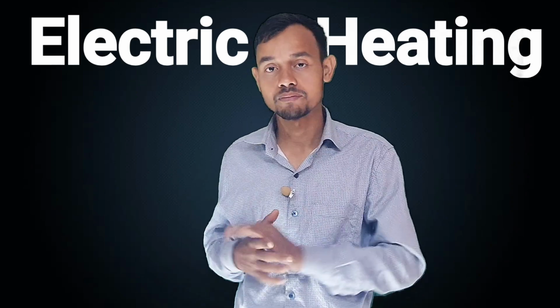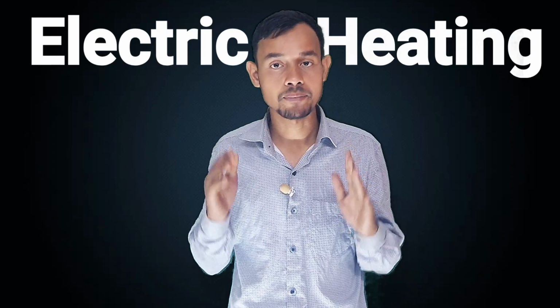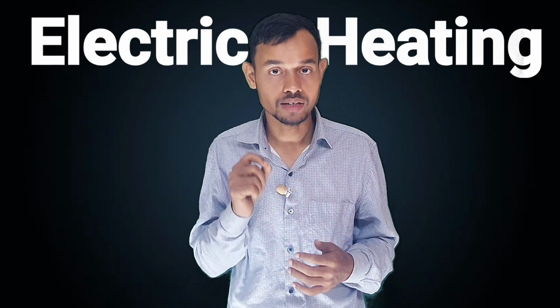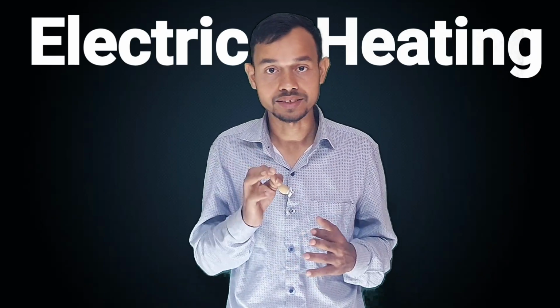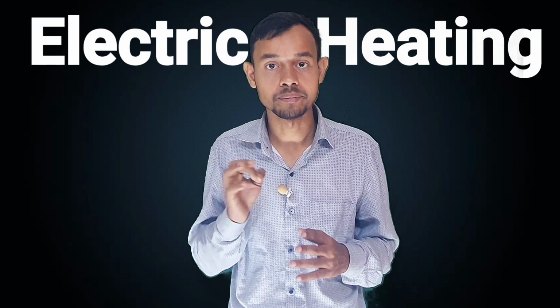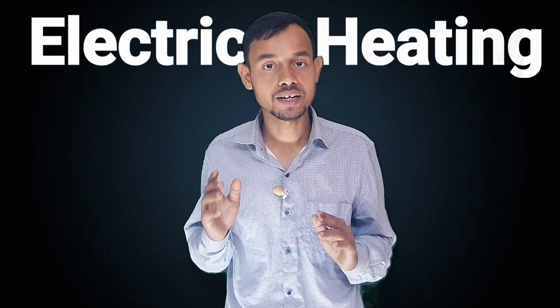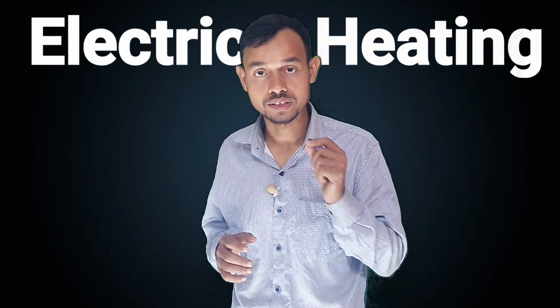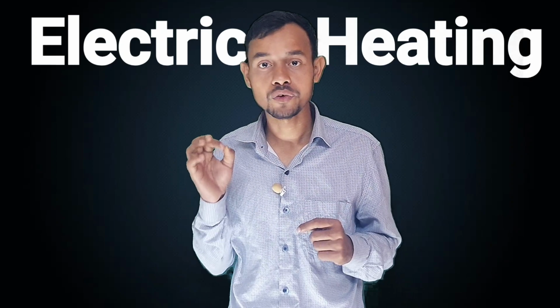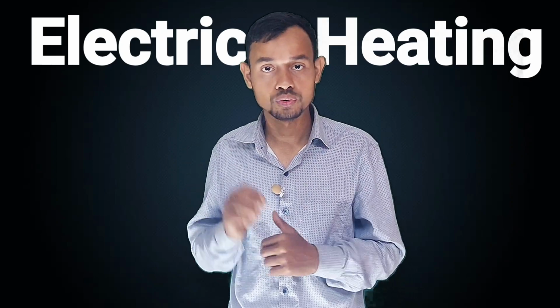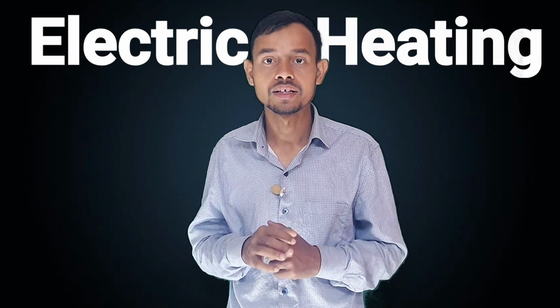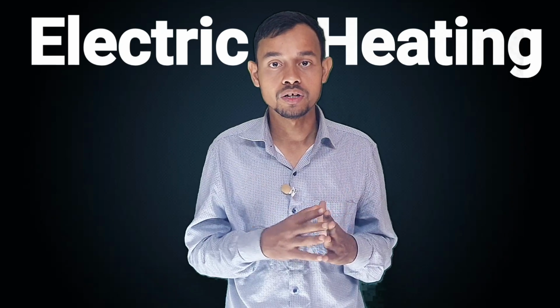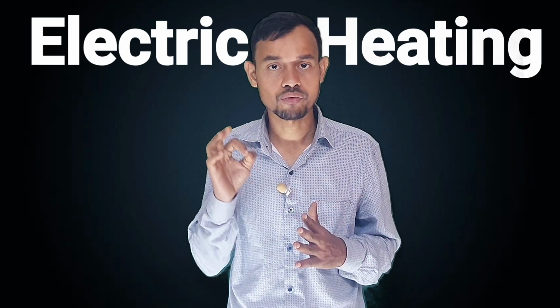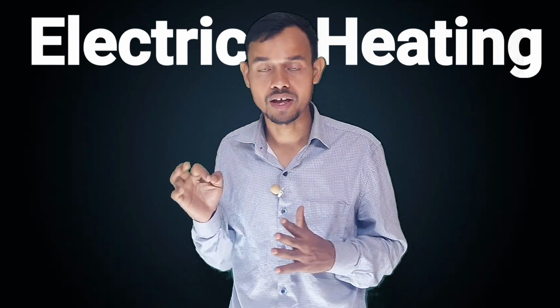Okay, for example, this heating mat covers 1 square meter and contains around 13 meters of cable. The cable has a resistance of 246 ohms. If we connect this to a 230 volt supply, the current demand will be roughly 0.935 ampere.